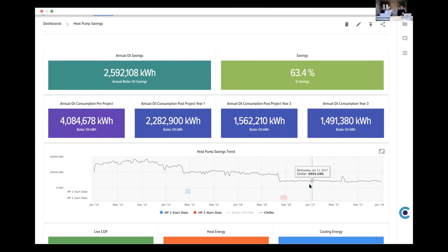You can see this huge drop in kilowatt oil from the boiler as soon as that heat pump went in, and that continued for the next couple of years - some huge savings involved there, 63.4% savings. Then that building actually expanded a year later, its footprint grew, its heating and cooling demands increased, and we installed a second heat pump, which further decreased the consumption of their chillers on site. So you can see that initial drop from heat pump 1 being installed, and then another drop from heat pump 2 being installed. It really is a game changer technology for decarbonization for our clients at the moment.